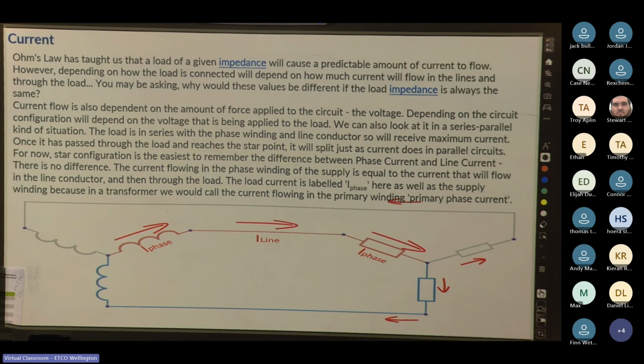Depending on the circuit configuration will depend on the voltage applied to that load. We can also look at a series-parallel situation. The load is in series with the phase winding and line conductor, so it will receive maximum current. Once it has passed through the load, it reaches the star point and will split as current does in parallel circuits. So for now, star configuration is the easiest to remember the difference between phase current and line current.